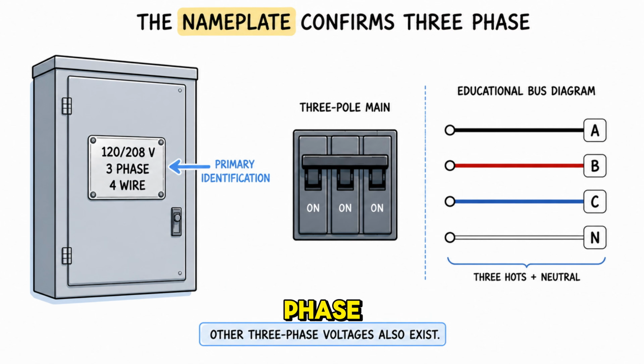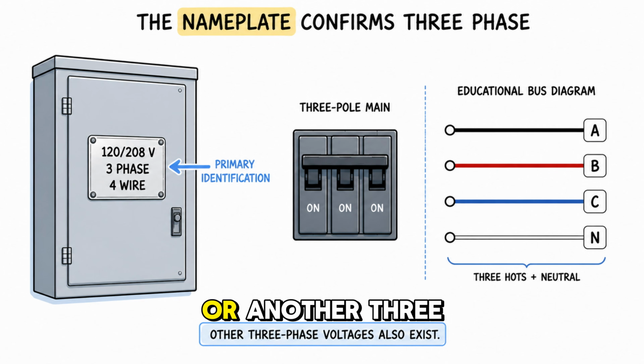A complete three-phase panel normally has three hot bus bars and a three-pole main disconnect. Its label may state 120 and 208 volts, three-phase, and four-wire, or another three-phase voltage arrangement. The label is more reliable than simply looking at the breaker handles.